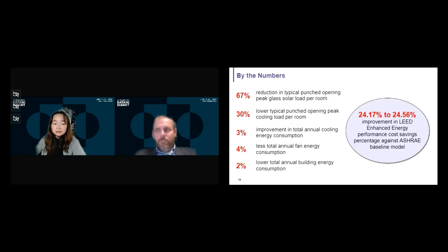At the end of the glazing study, we reduced the peak solar load per room and were able to reduce overall building consumption. The overall building consumption is much smaller compared to peak load, because peak load may only occur for a couple hours in the afternoon in July, but it's still significant since that's what we use to size our heating and cooling systems. This helped us reduce our overall system footprint and mechanical room sizes.